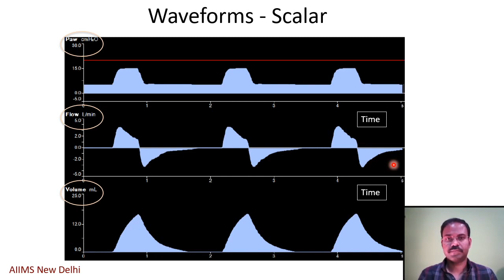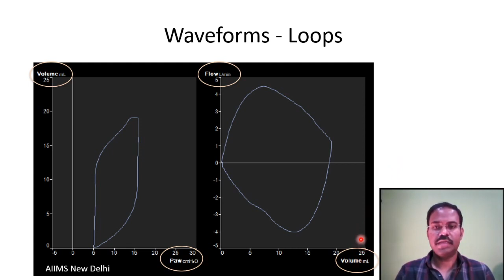It's important to note that the flow time scalar will have flow waveforms both above and below the x-axis, that is the time axis, whereas the other two will have only positive deflection above the time axis when you are dealing with a patient on positive pressure ventilation. If you leave aside time and plot the relationship of pressure and volume, you get a pressure volume loop. Similarly, if you plot volume and flow, you get a flow volume loop. It's important to note that in the pressure volume loop, the volume is on the y-axis, whereas in the flow volume loop, the volume is on the x-axis.